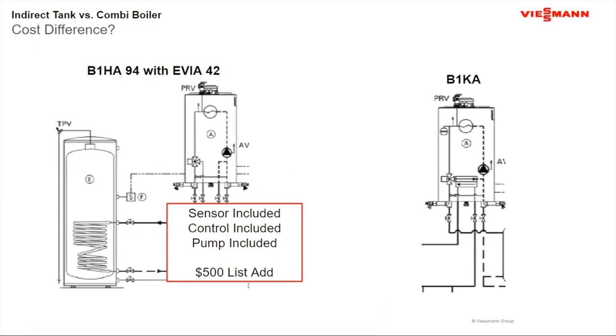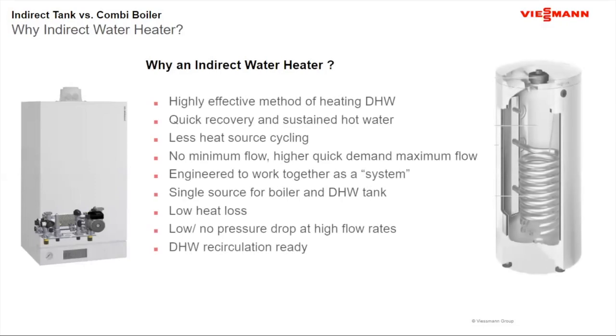But again, when we start to look at going with the boiler with the indirect versus the combi unit, the price increase is not a major jump when you look at a project that you're expecting to last for a long life cycle. So comparing the two, back to my question of why an indirect? It's a highly effective method of heating domestic hot water, and it brings a lot of positives to the table when we look at the methodology of heating the water.